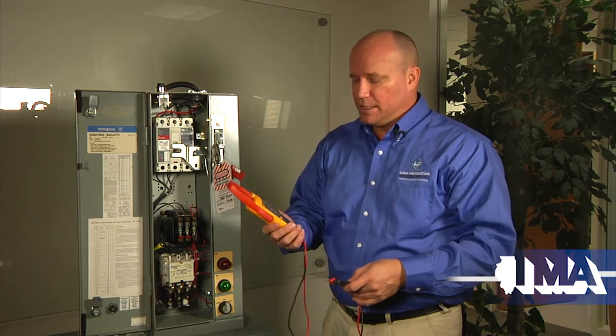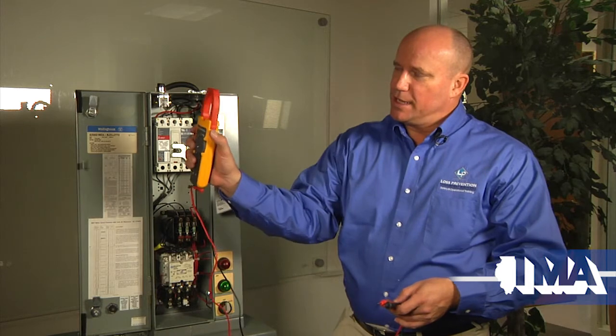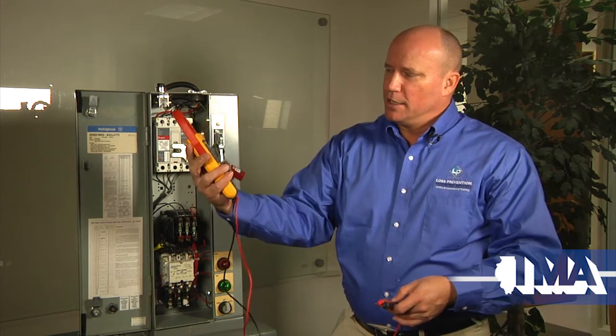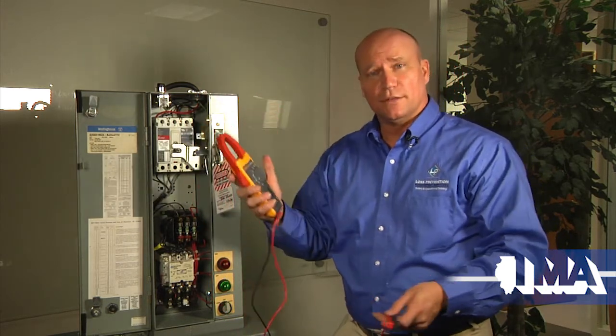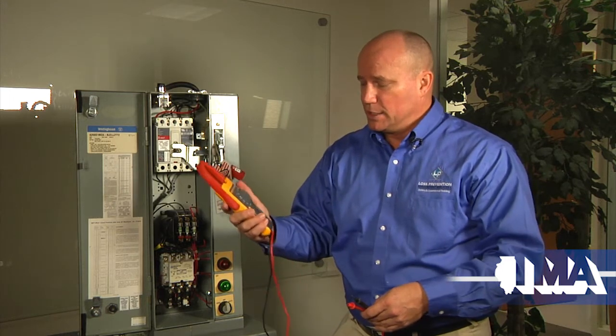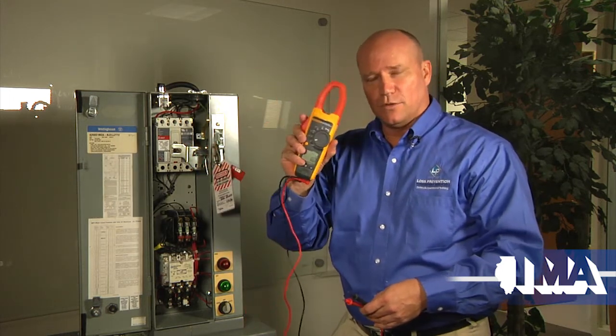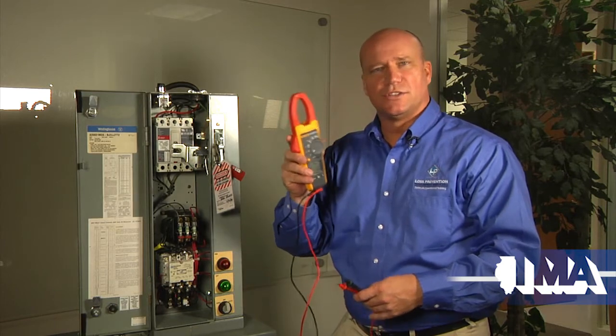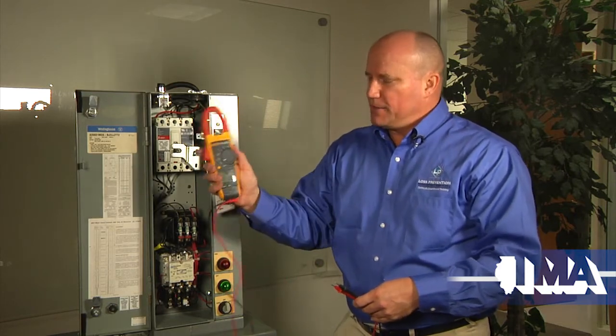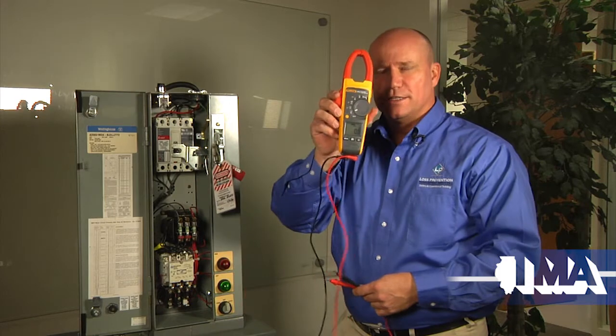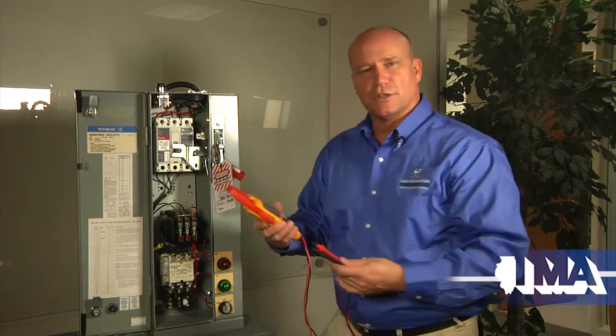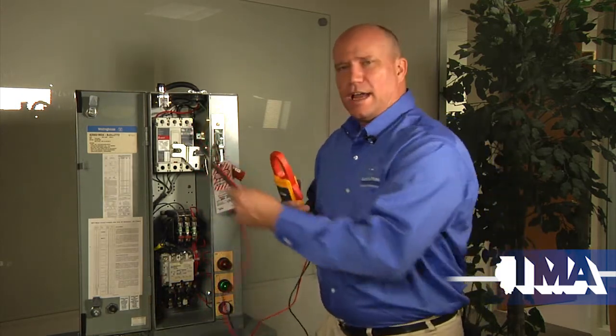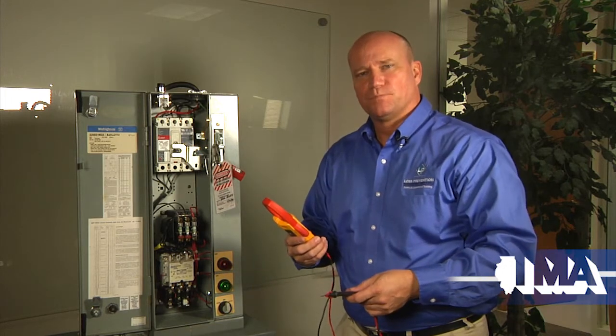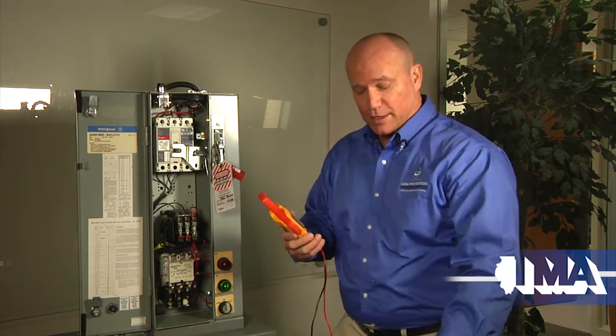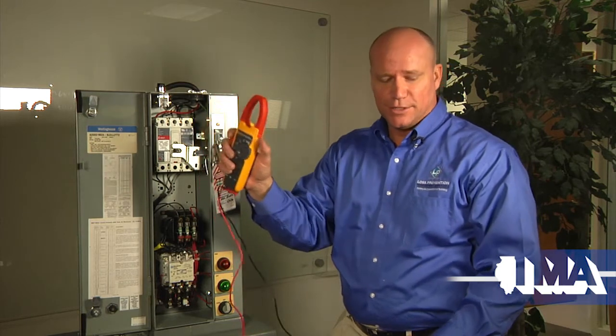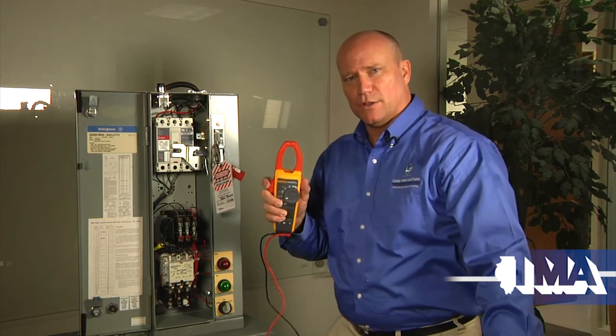The other reason is that every meter, and in this case this meter, has a hold button to lock in a reading so you can document it, or whatever the reason. This will warn you by giving a beep. Some meters don't do that. So if that's on hold and it's held on 0 volts, every reading thereafter is going to be 0 volts. That's something you're not going to catch until you do the last live check. I've seen it over and over again that people accidentally hit that button. It's easier to do when you have your gloves on with the leather gauntlets.